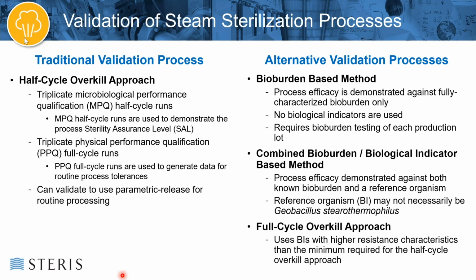And then finally, there's the full cycle approach to the overkill method, which is in the same annex as the half cycle. And this uses a BI with higher resistance characteristics than the minimum required for the half cycle overkill approach. So there's a series of industry standards out there that deal with how to manufacture biological indicators and what the minimum requirements are. And those standards state that for steam sterilization, you have to have a minimum of, I believe it's 1 times 10 to the 6th organisms, which is essentially 1 million organisms or more on each BI. And then the D value or the resistance of that organism must be greater than or equal to 1.5 minutes, which means that it takes 1.5 minutes at 121 degrees Celsius to reduce the population from 10 to the 6th down to 10 to the 5th.